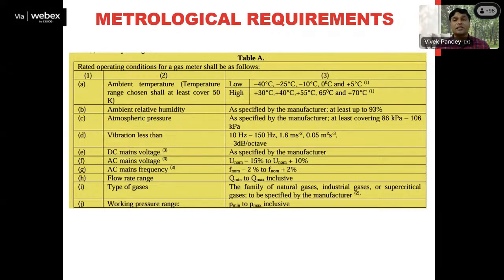If a manufacturer is deciding the temperature range, it must be selected between the values specified here in the table. The lower temperature can be prescribed as minus 40 degrees Celsius, minus 25 degrees Celsius, minus 10 degrees Celsius, 0 degrees Celsius, and 5 degrees Celsius. And the higher temperature can be selected between these values: 30 degrees Celsius, 40 degrees Celsius, 55 degrees Celsius, 65 degrees Celsius, and 70 degrees Celsius.